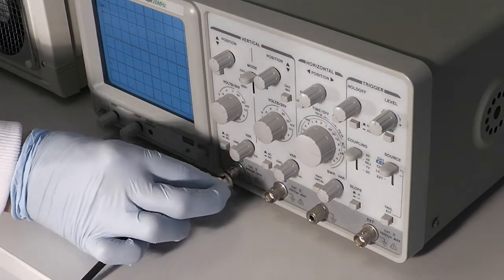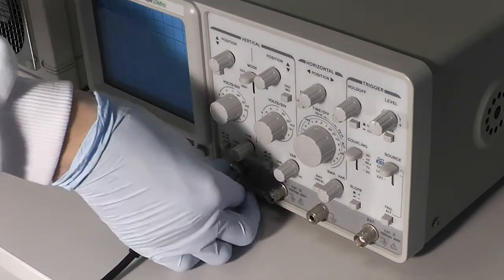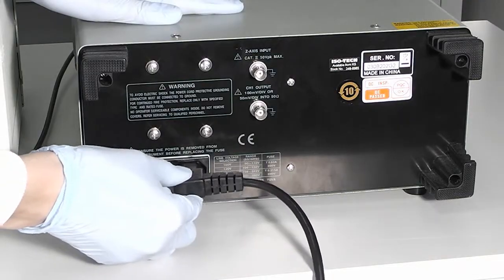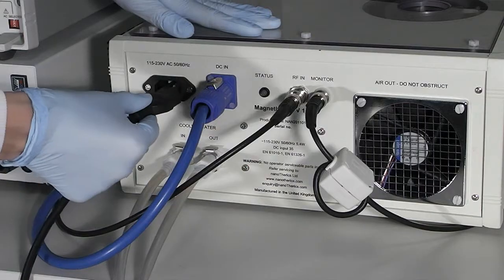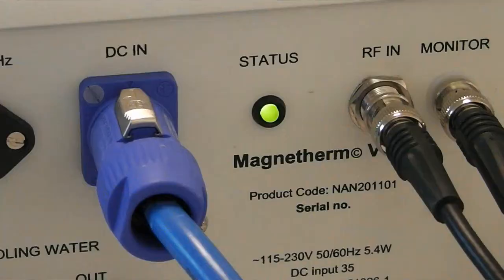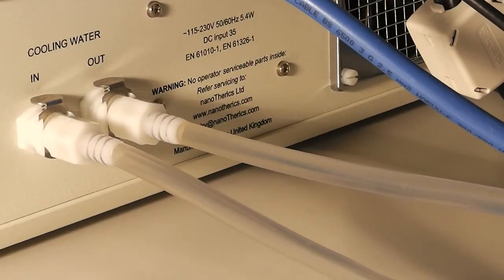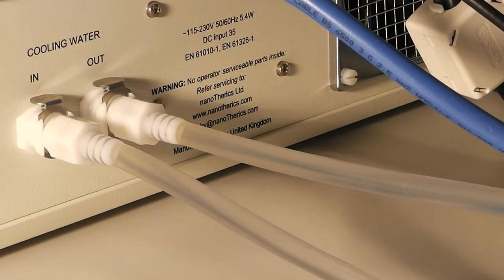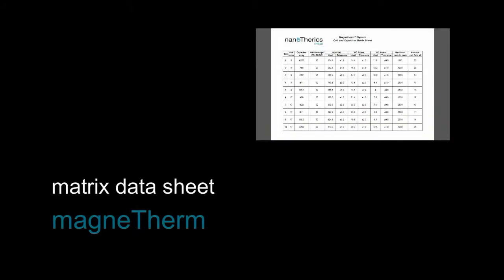Before switching on the system to run your magnetic nanoparticle samples, make sure everything is connected properly once again. Especially make sure that the water inlet and outlet is okay, as the coil enclosure will not switch on if they are not connected properly, or if the water inlet pressure is below or too far above 320 milliliters per minute. After that, look into the reference matrix sheet for your magneTherm system.